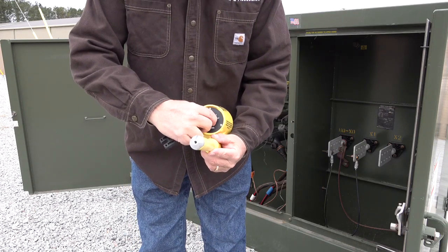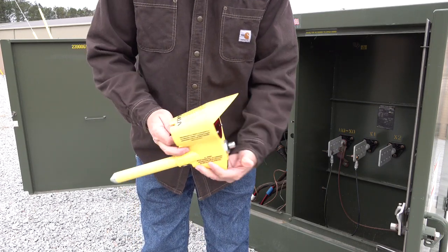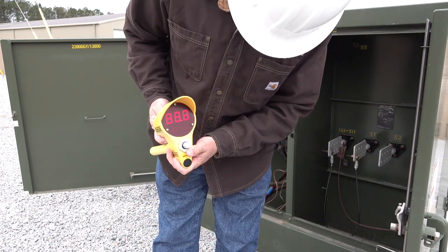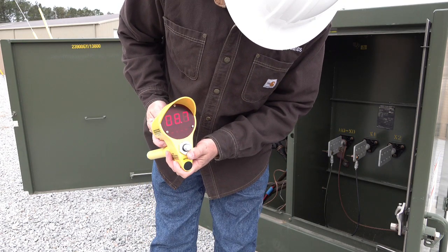As the manufacturer of the VD1000, we highly recommend that the device is turned to the test position and held there until the battery voltage is displayed. You'll notice on this device the battery voltage reads 8.7 volts. This is considered good. We suggest if the reading is 7 volts or less to go ahead and replace the battery. If the battery voltage is allowed to go as low as 6.5 volts, the VD1000 is designed to shut off and no longer function.